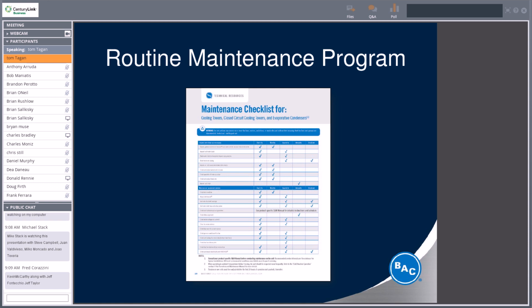It recommends that you clean the fan motor exterior, check it for proper rotation, check the general condition of the fan. Most manufacturers have 3 types of fans. Now you have your standard aluminum, you have a standard galvanized fan, an aluminum fan, and a lot of the ultra quiet or whisper quiet fans that are used today are actually a fiberglass or a poly material.